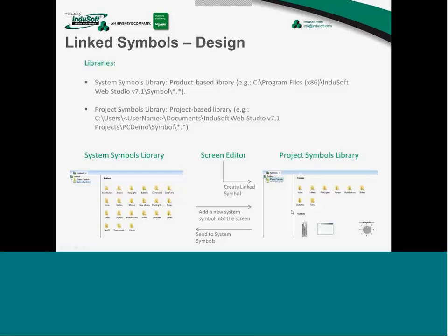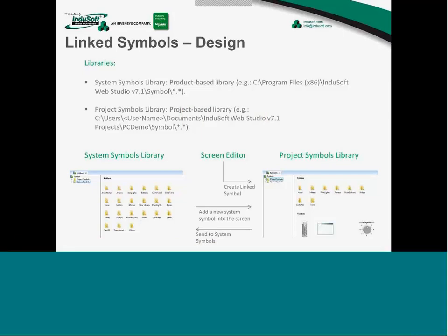If you create or modify a symbol and you want to share it with different projects, you can right click on the symbol and use the option Send to System Symbols, and InduSoft copies your symbol from the project to the library. So the bottom line is you have two libraries, one for the product, which is generic for all the projects. And as soon as you use a symbol in your project, it comes to your project and is encapsulated into your project in the subfolder Symbol.